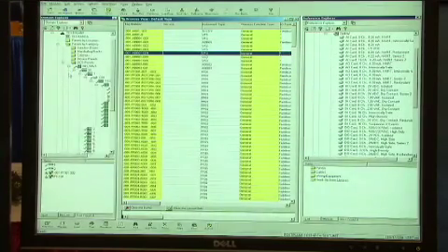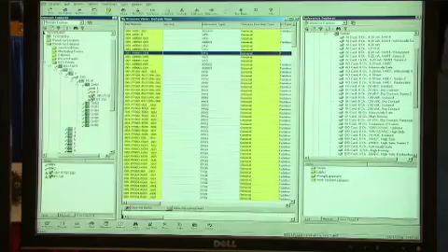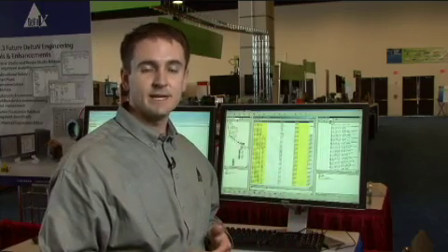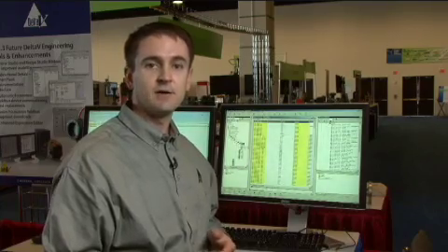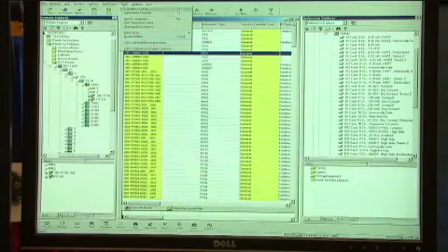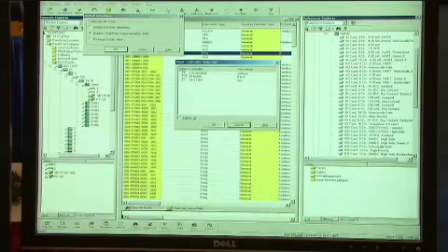So now going over, I can show you an example DeltaV configuration of a controller, I/O carrier, I/O cards, and instrumentation. You would continue to build up this information and configuration within SPI, and then once you are done, we can transfer this information to DeltaV by publishing the data from SmartPlant Instrumentation in an XML file format. So using the built-in interface within SmartPlant Instrumentation, I select the controller that I've configured in SPI, and I publish this data in XML file format.